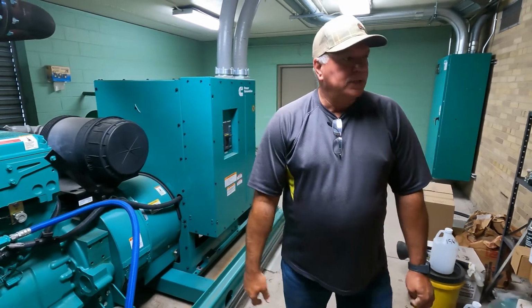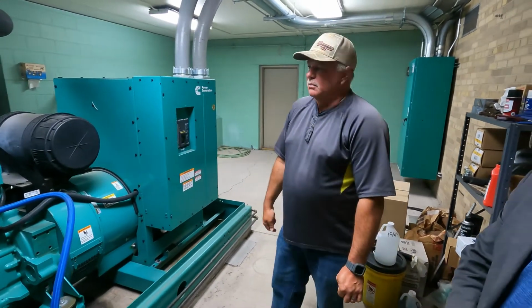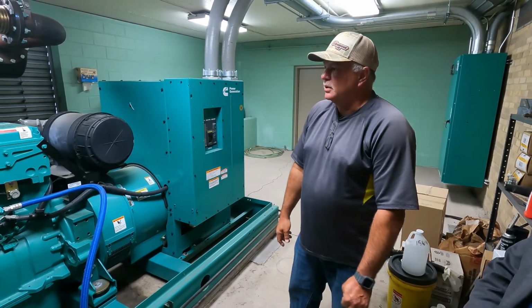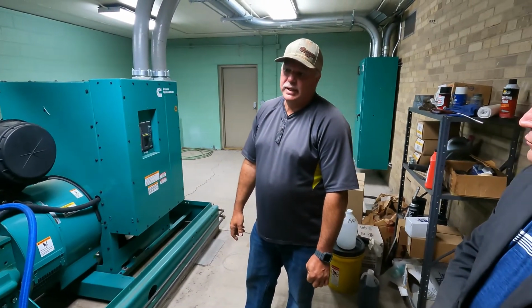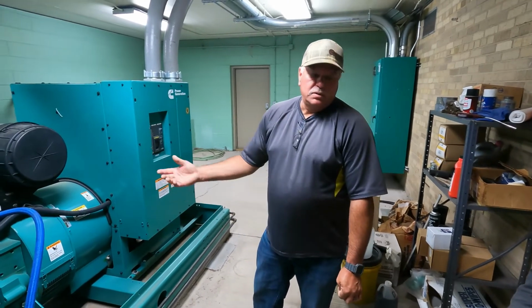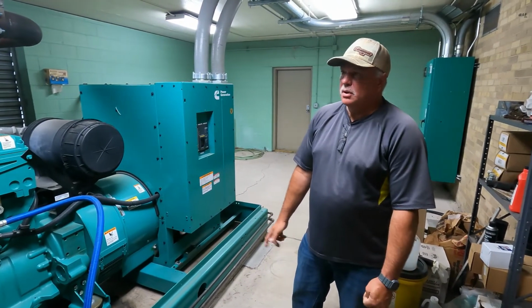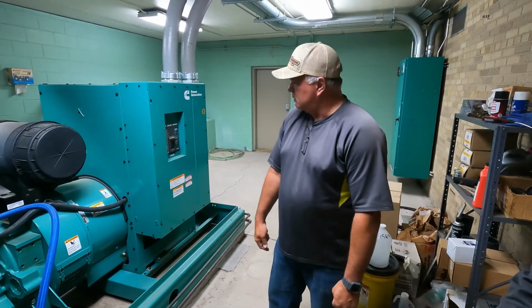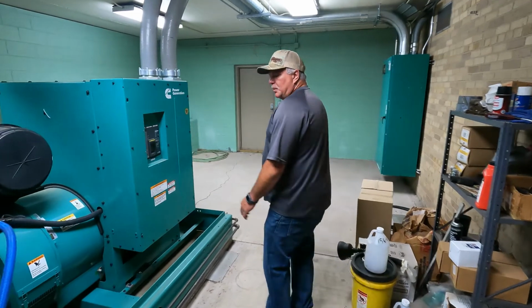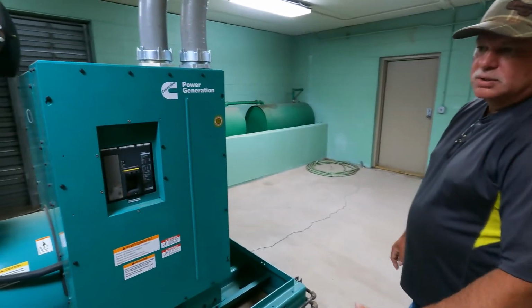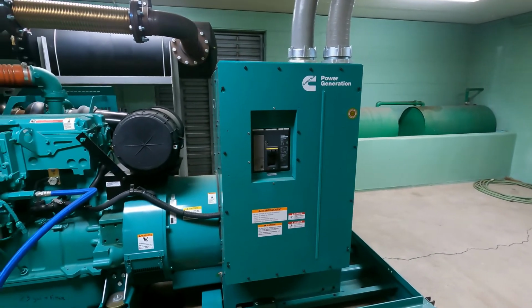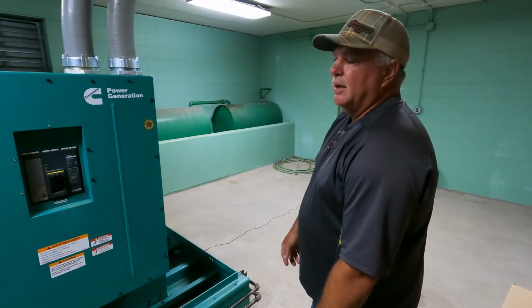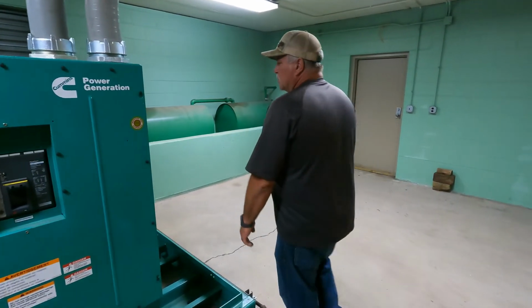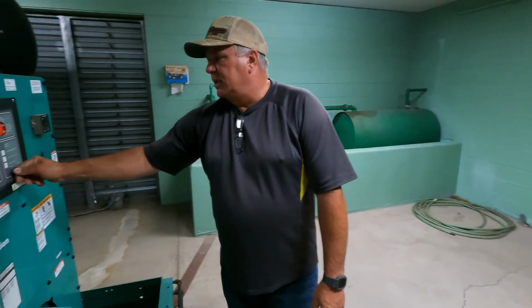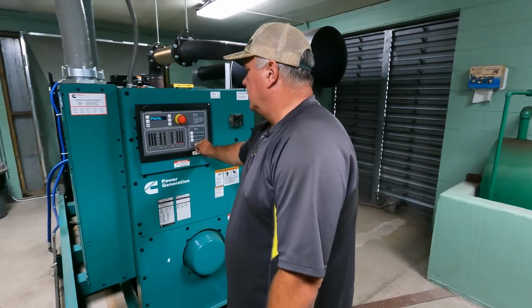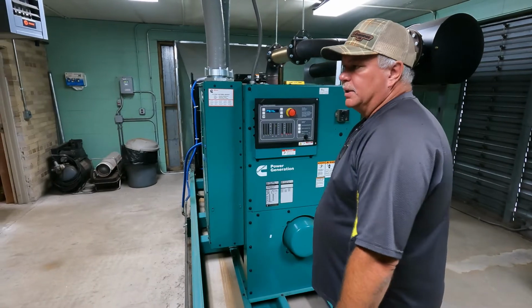Is this a natural gas pump? This is actually fuel oil. Oh, fuel oil. Yeah, it was just replaced a couple of years ago, actually. I'm not quite sure if they studied switching to natural gas or why not, but it's currently fuel oil. It always has been, even the old ones. The operator, as far as the mechanic, we do keep track of hours on the generator, and every so many hours we change the oil, the fuel filters, the antifreeze filters. We monitor hours through the main panel, and if there are any alarms, the generator would show them on this digital screen as well.